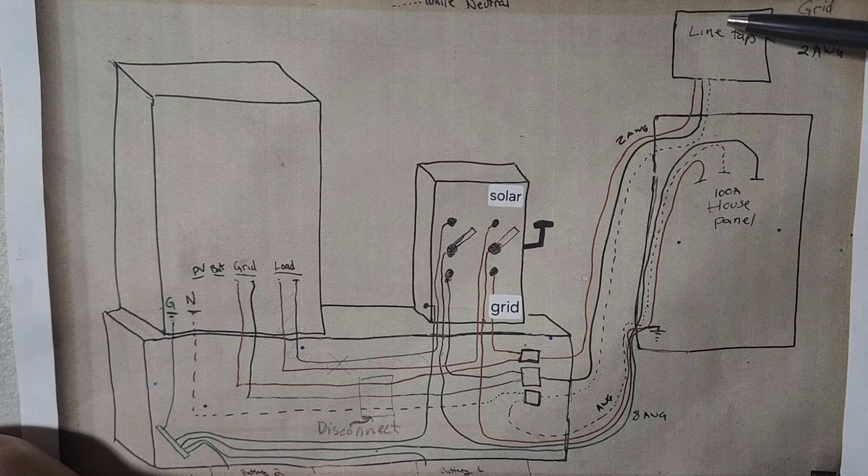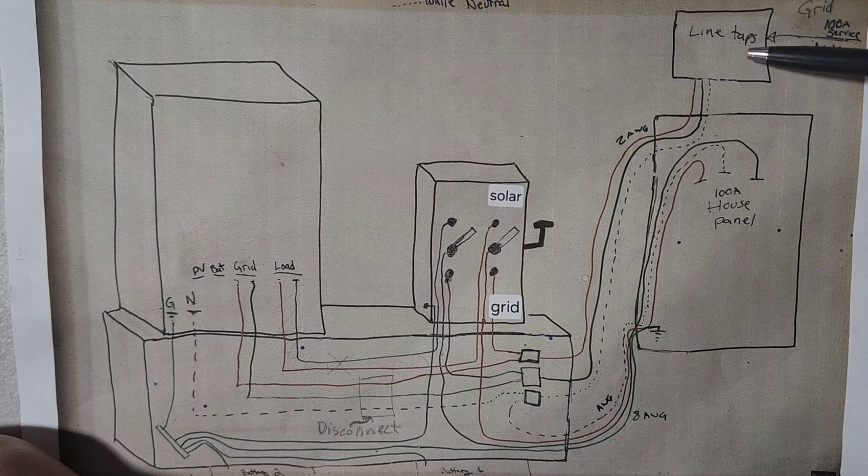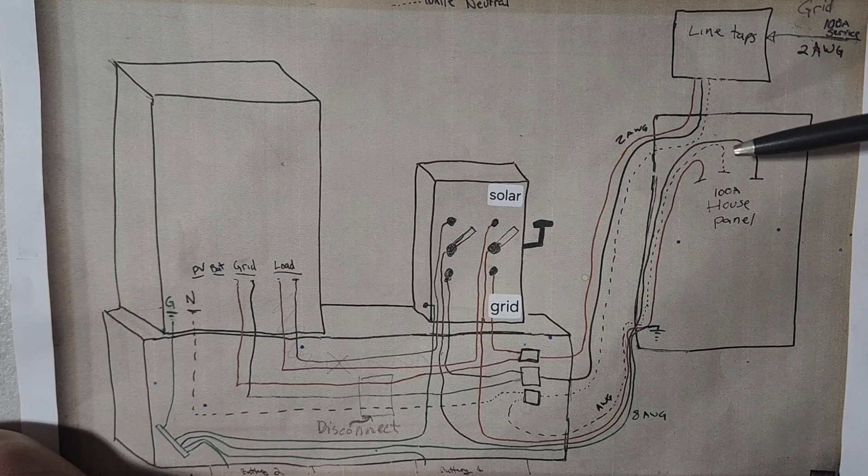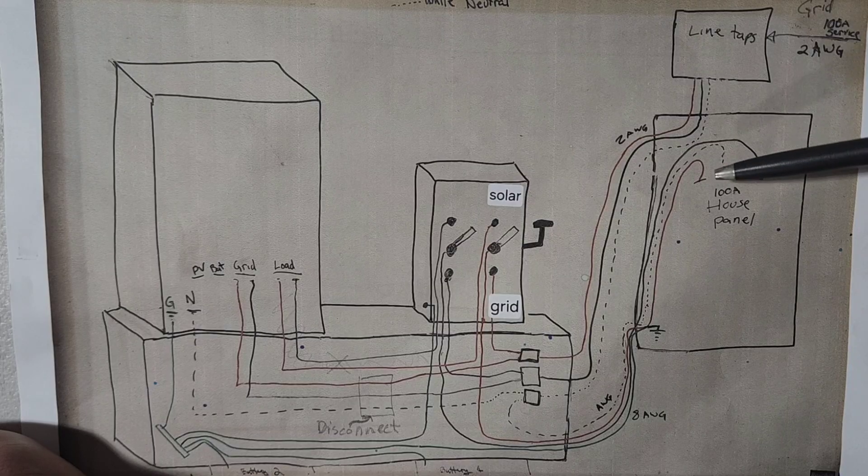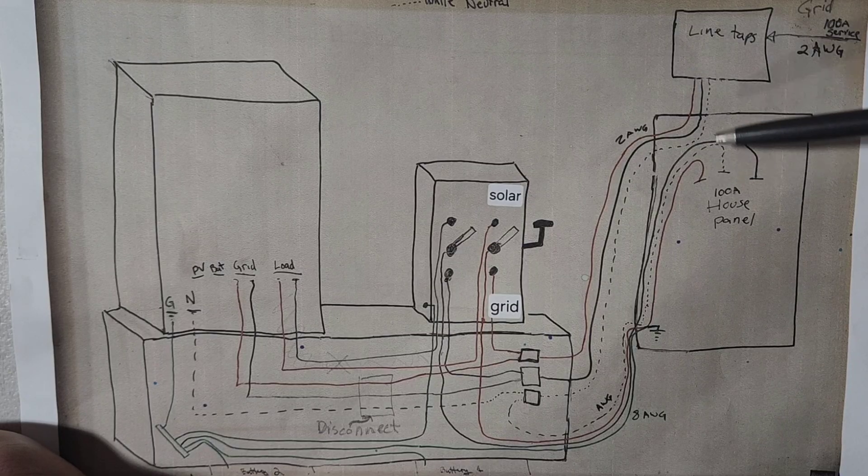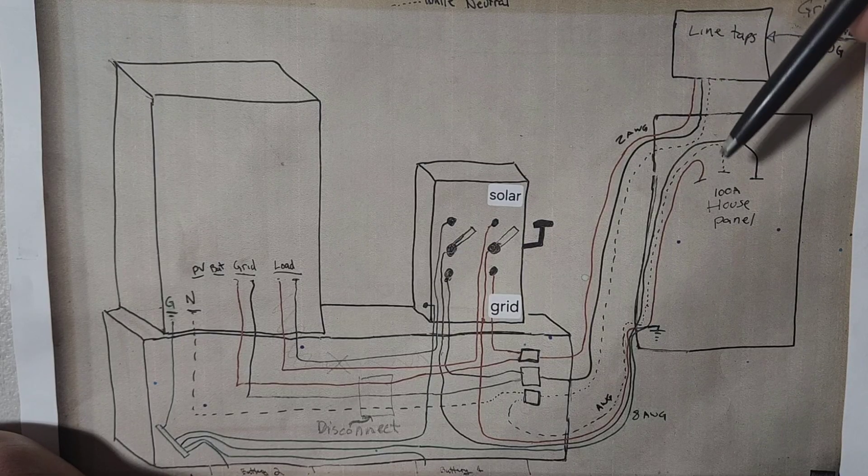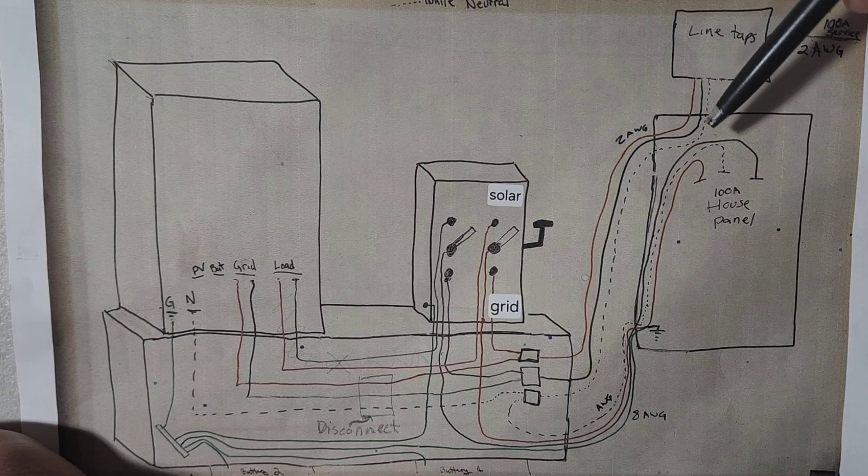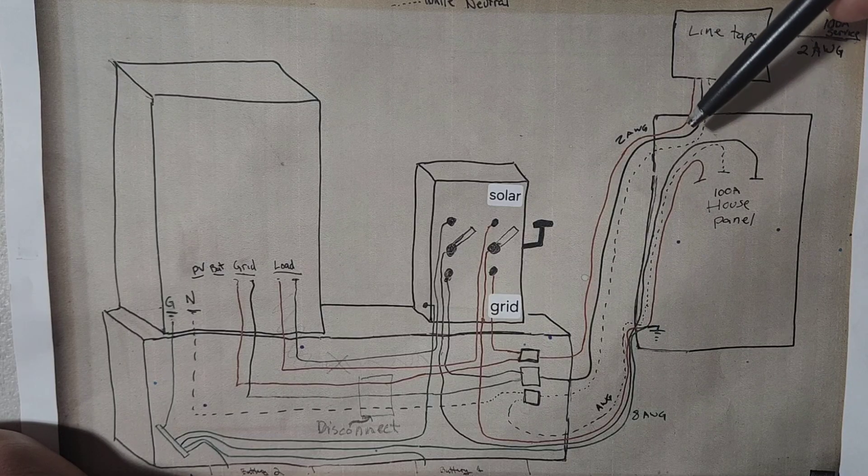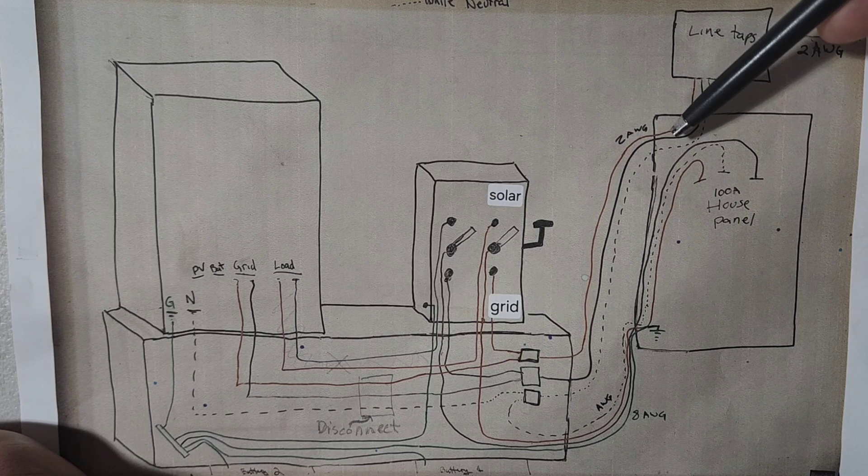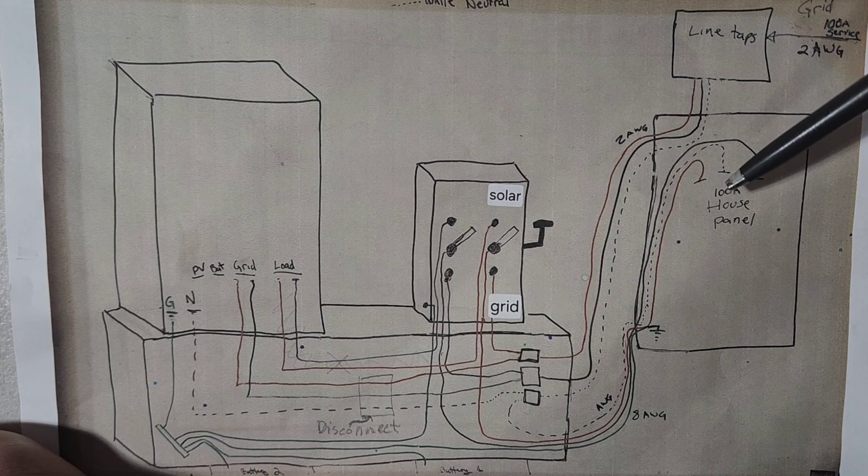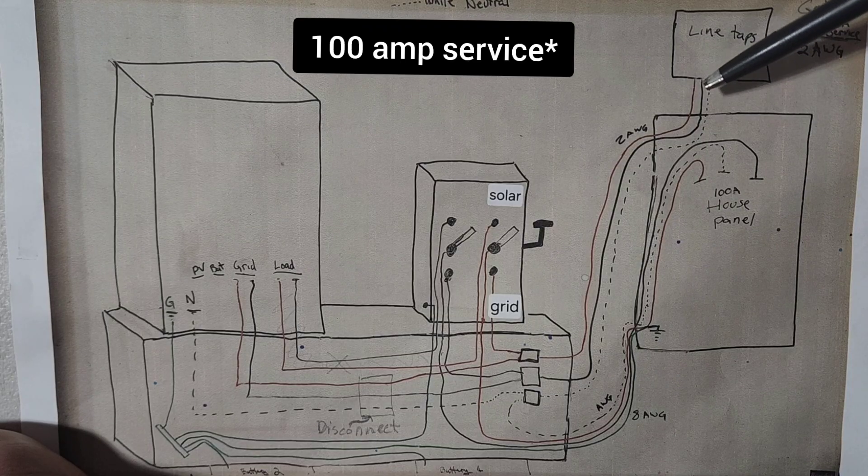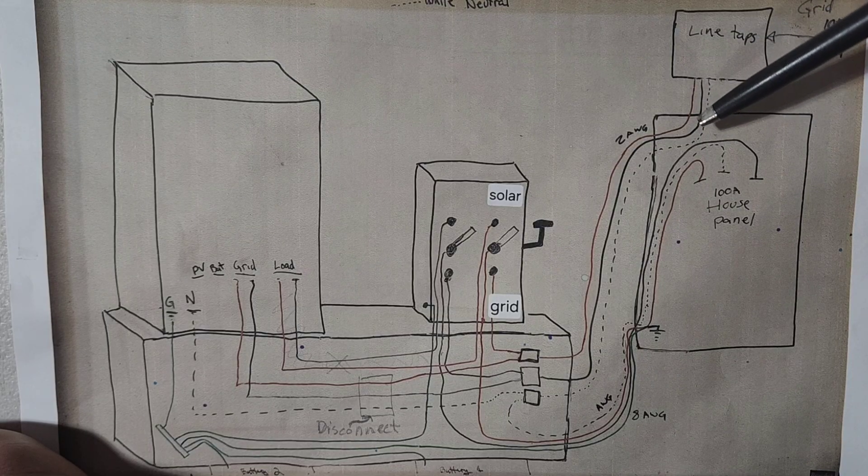There's actually a shutoff switch above here on the outside of my house. So basically what I did in my setup, and your house is maybe a little bit different than this, but I disconnected my lugs that were feeding in here and then I added what's called a Polaris connector. It allowed me to extend these wires, and these are two gauge wires for my house because I have a hundred amp house electrical panel.